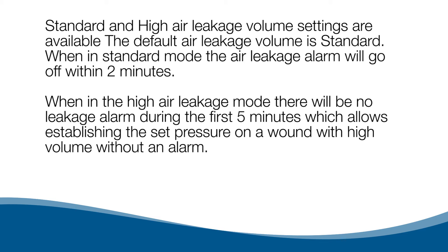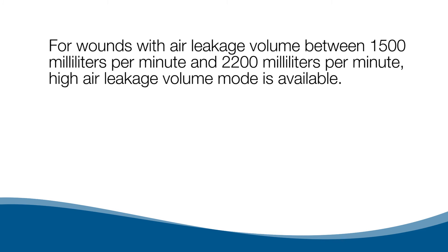When in the high air leakage mode, there will be no leakage alarm during the first 5 minutes, which allows establishing the set pressure on a wound with high volume without an alarm. For wounds with air leakage volume between 1500 milliliters per minute and 2200 milliliters per minute, high air leakage volume mode is available.